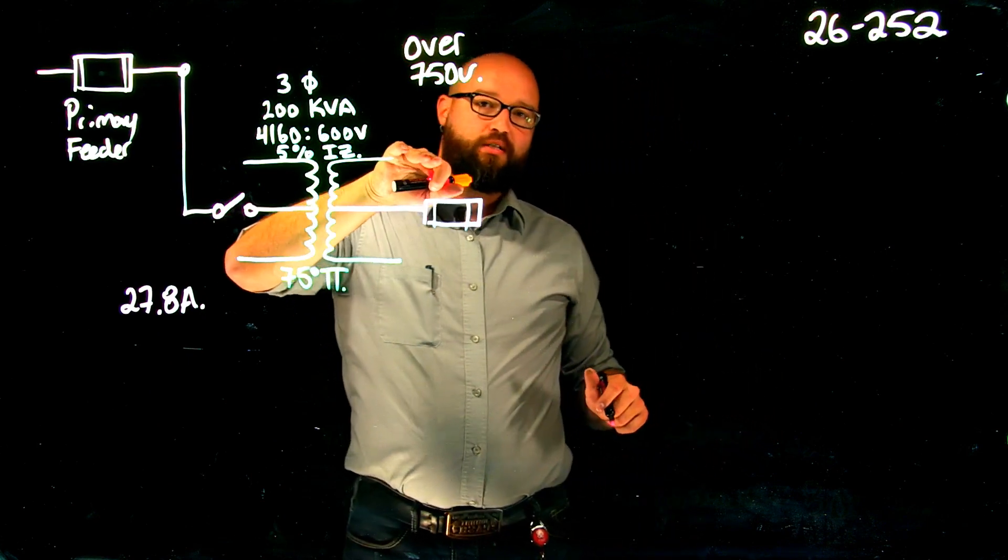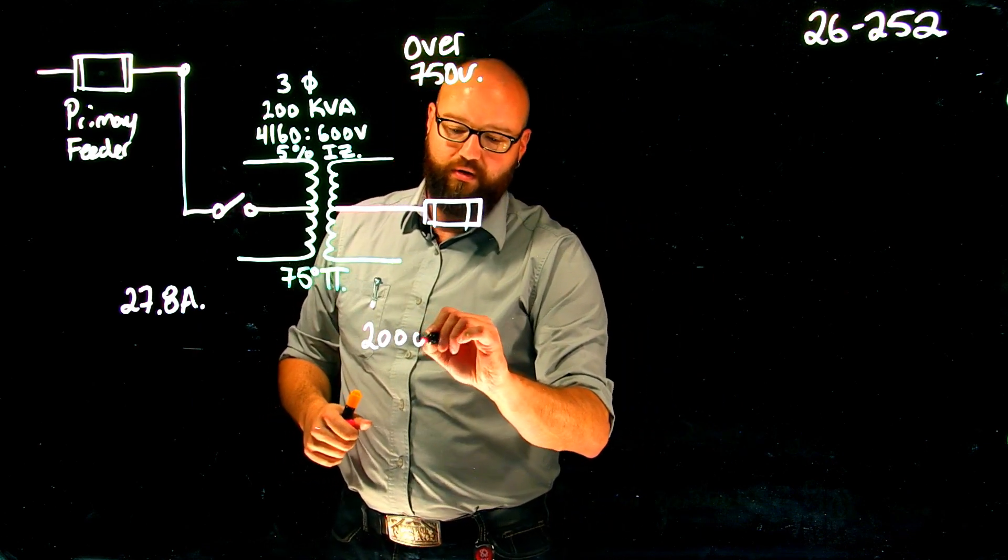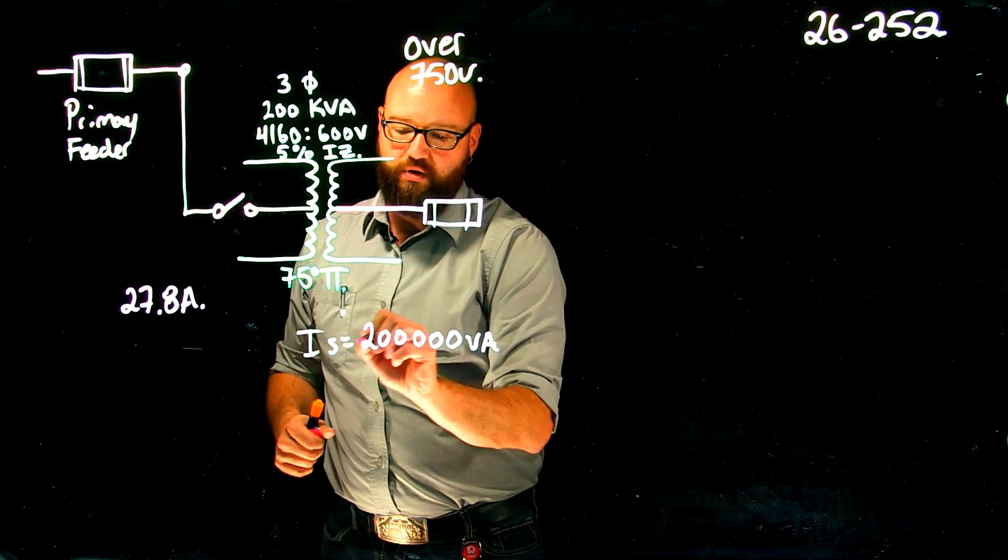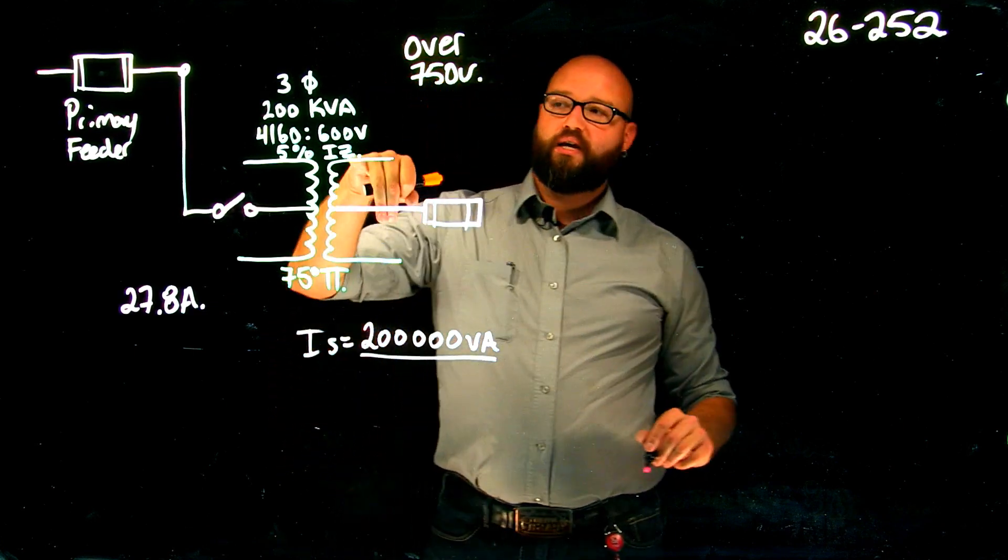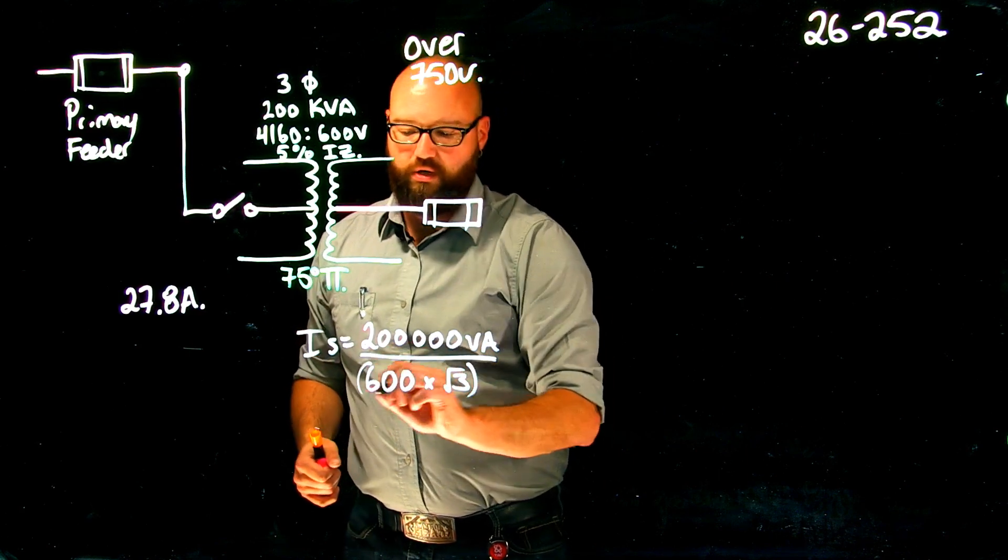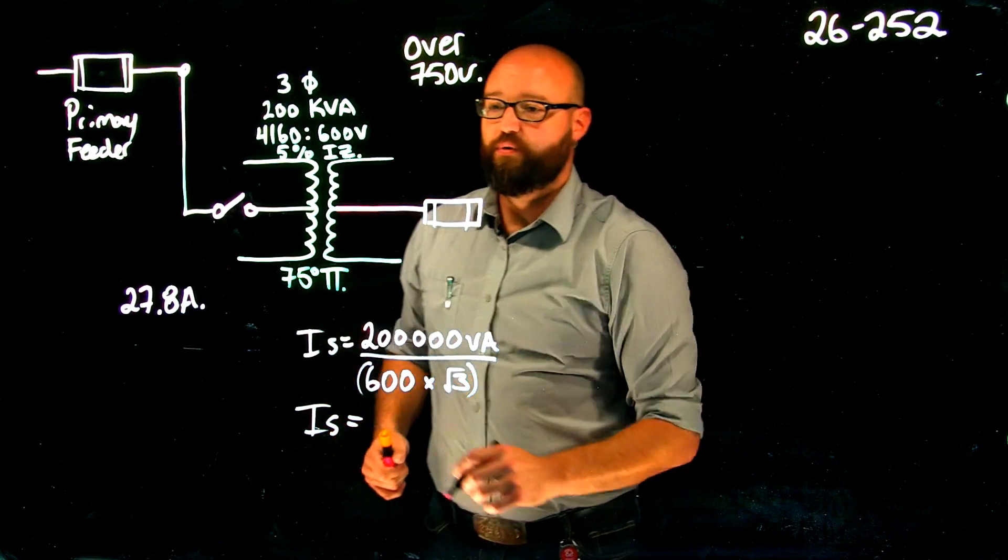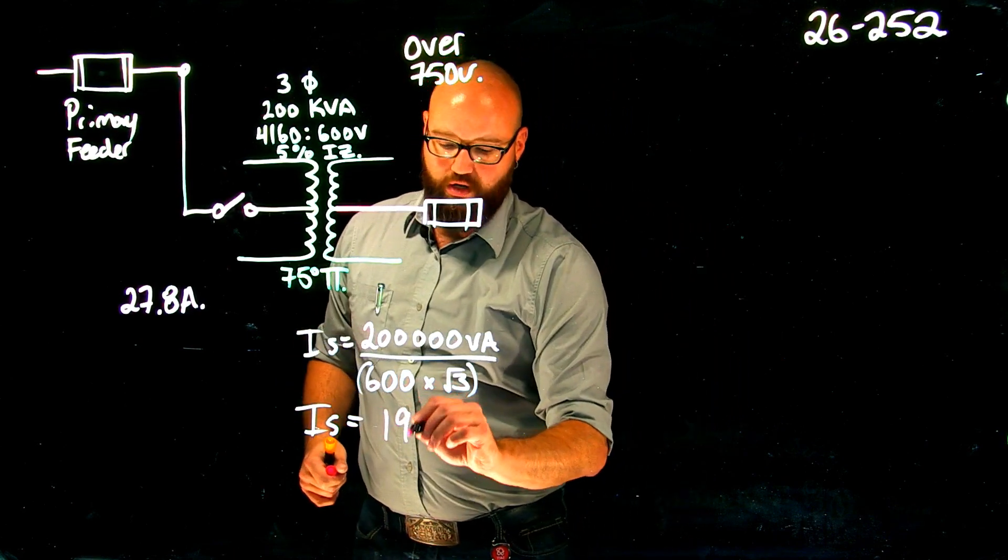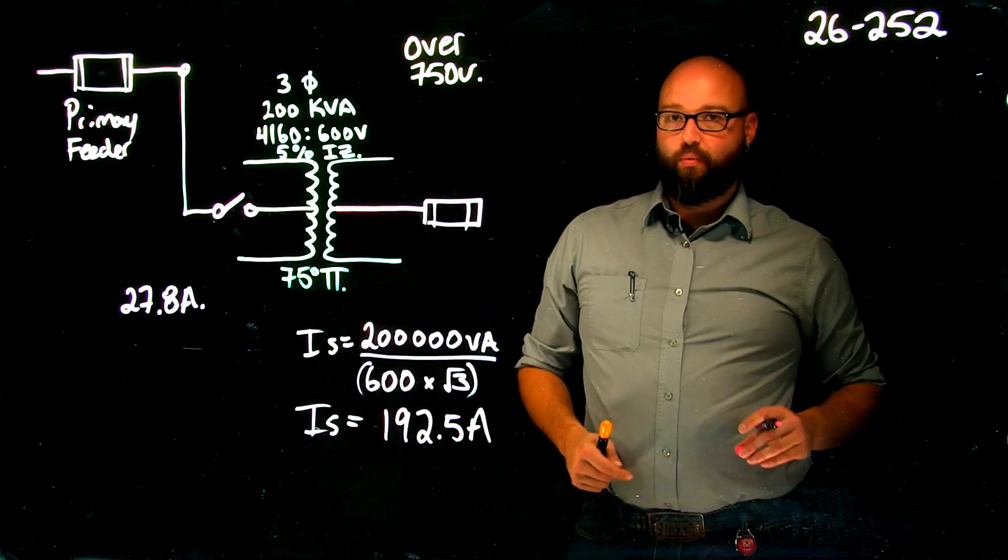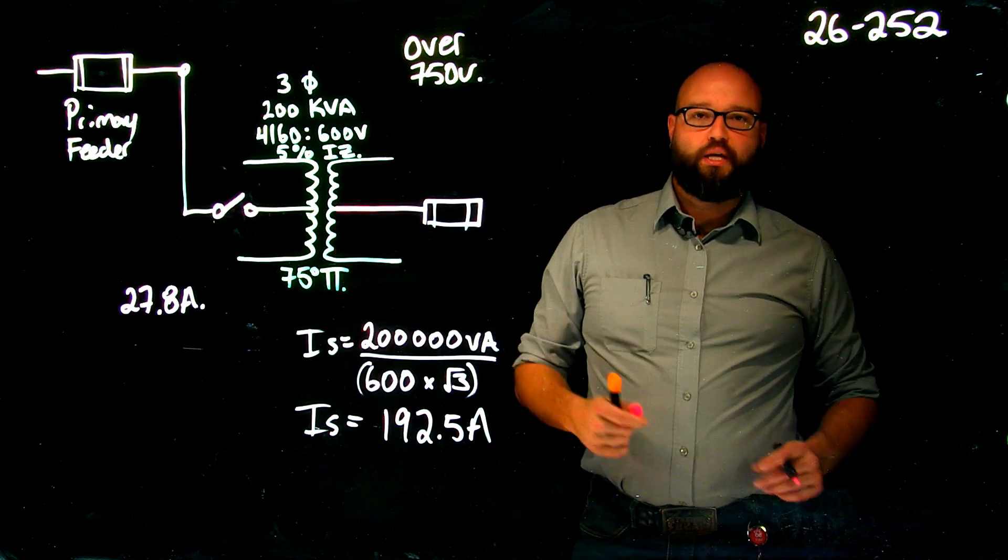We need to figure out what our secondary rated current is as well. We have our 200,000 VA divided by our secondary line voltage of 600 times root three, gives me a rated secondary current of around 192.5 amps rated on the secondary. So we're going to take this information. We're going to go to Table 450.3 and look at Table 450.3.